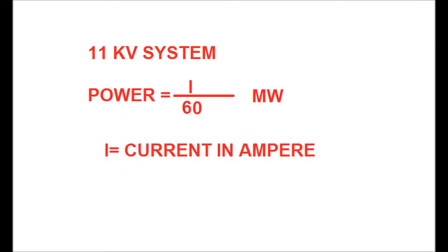For an 11 kV system, if current I is a known quantity in amperes, then if you divide I by a factor of 60, you can get the value of power in megawatts. That is the thumb rule.